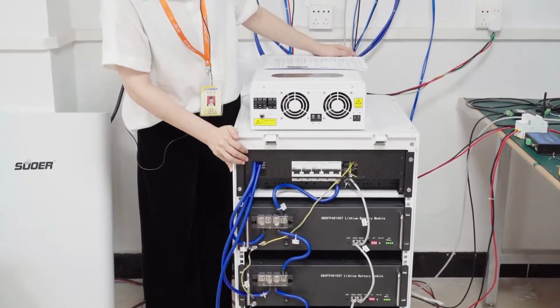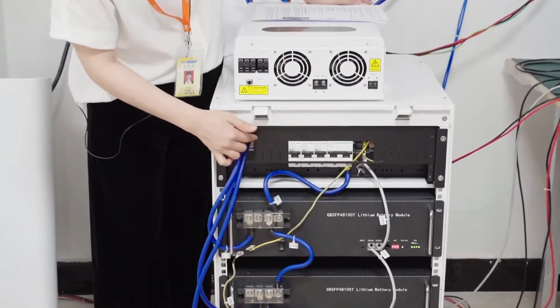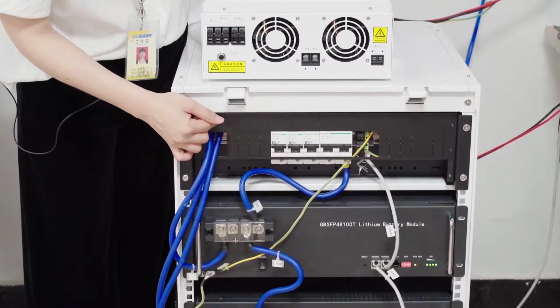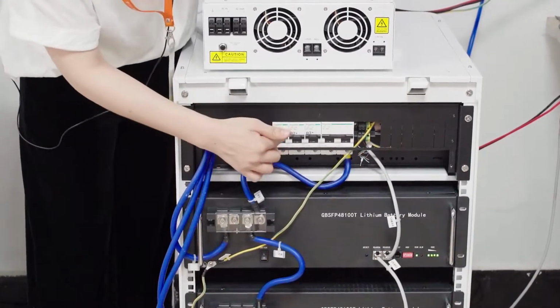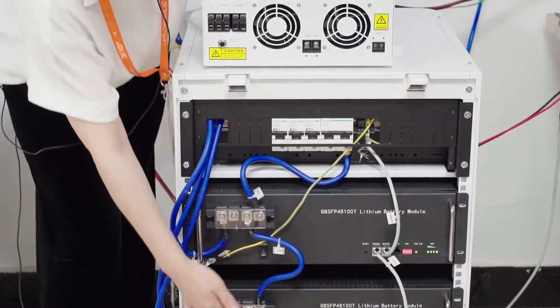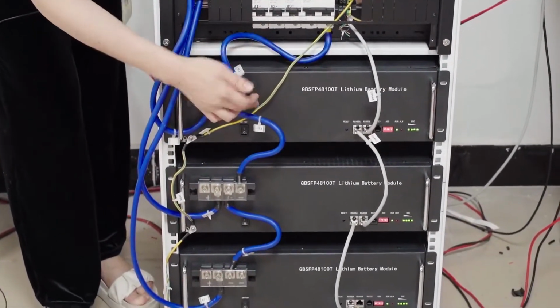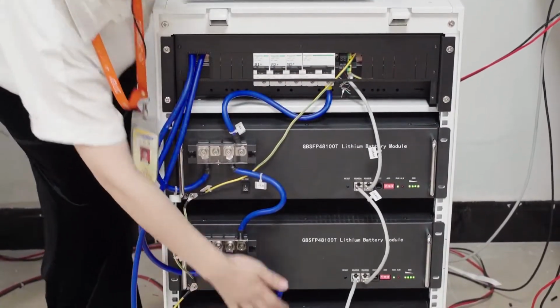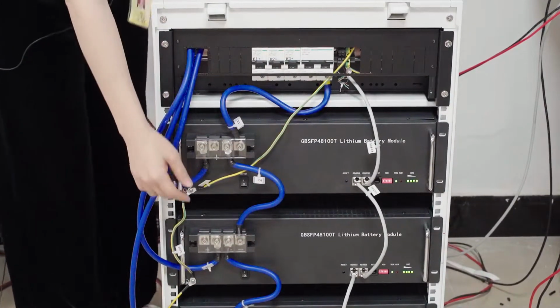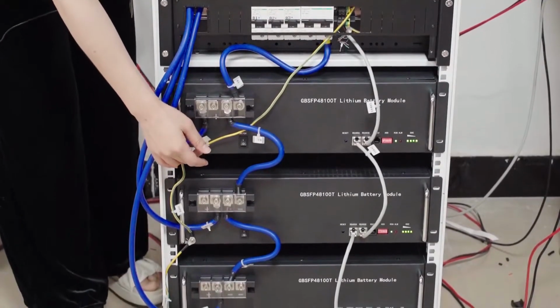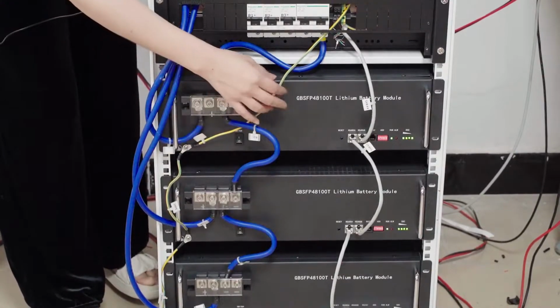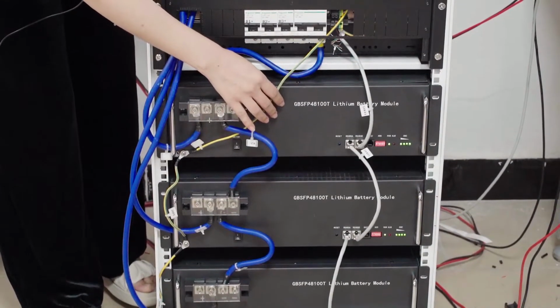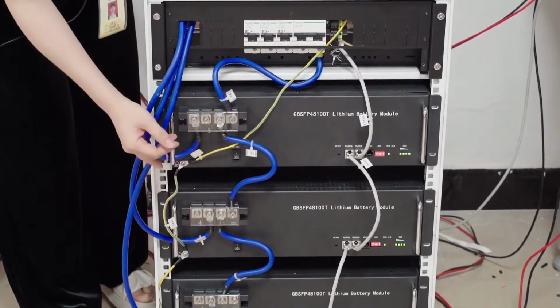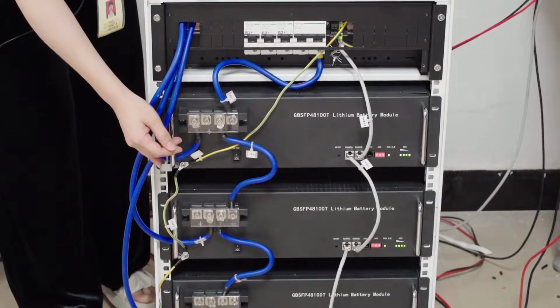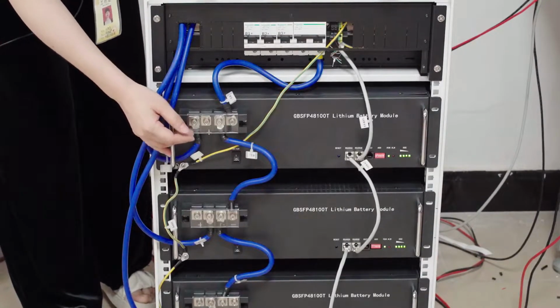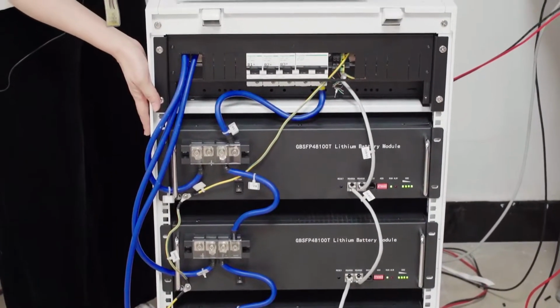These cabinets also have power distribution units. They can protect the batteries from over-current and short-circuit. The switches control the 3 batteries one by one: 1, 2, 3. And below are the lithium iron phosphate batteries. It's 48 VDC and 100 AH per unit. You can see there are 3 units here. Then its total is 15 kilowatt hours. You can increase or decrease the number of the battery packs according to your demand.